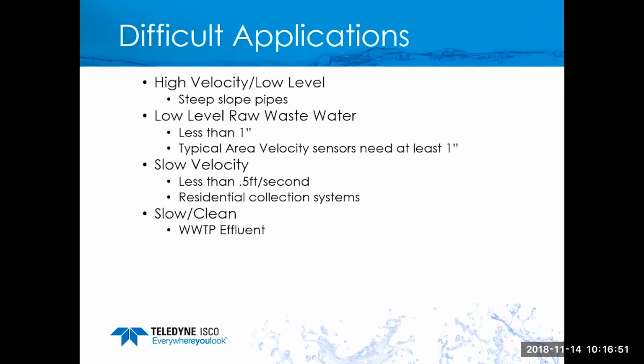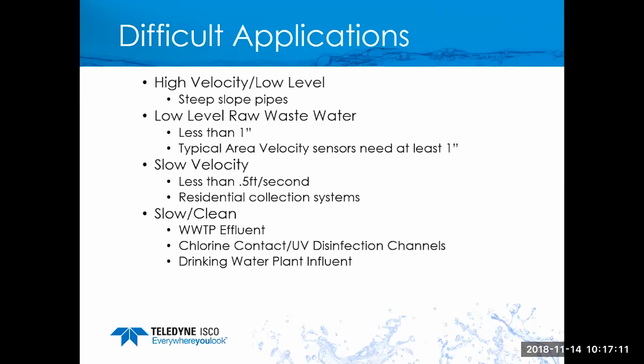Wastewater effluent plants are very clean, hopefully, if they did the job right, and a lot of times there's not a lot in there to see. Chlorine contact and UV disinfection channels are another big one that's popped up on the radar. A lot of times they want to monitor the UV channels to know how to dose or pace their lights. Then there's open channel drinking water going to plants. We did one down in Kansas, and it was 20 foot wide. They put 2 lasers to span that 20 foot width, and it's water coming into the drinking plant.